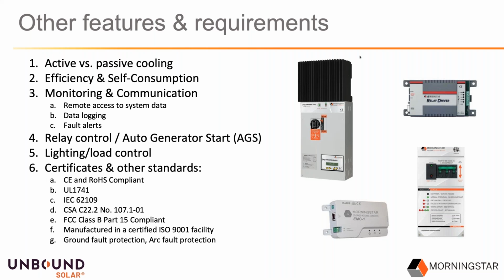That has a couple of drawbacks. A big one is that you're pulling in anything in the room, whether it's dust or other debris, and you're potentially blowing that across the circuit board, shortening the life of components. The fans are also another part that can wear out, and they have a parasitic self-draw. We're powering a fan that we wouldn't normally have to, so that has some self-loss, which leads into the second point, efficiency and self-consumption. Most modern MPPT controllers are going to be very high efficiency, probably 98 to 99%. Self-consumption should be low. It can depend on if you have a meter or something, but it's often a watt or less. But these are some of the things that you might compare at the initial stages if you're looking at different brands or different controllers.